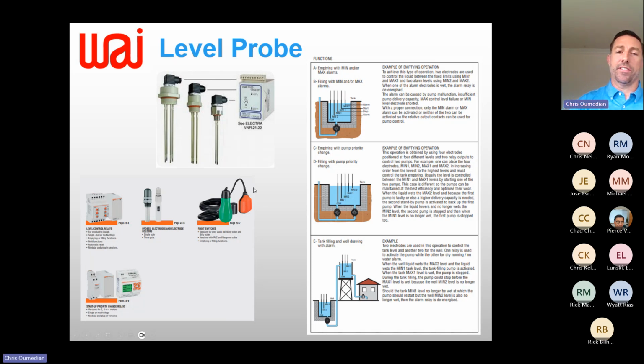It's not analog. The sensing device is just this tip. Once the media touches that tip, it doesn't matter if it goes above, once it touches the tip you get an output. So it's digital information, not analog. That's why on the right the probes are all different lengths. When you order these, you order them in whatever length you want for your high level, low level, mid level, or whatever.